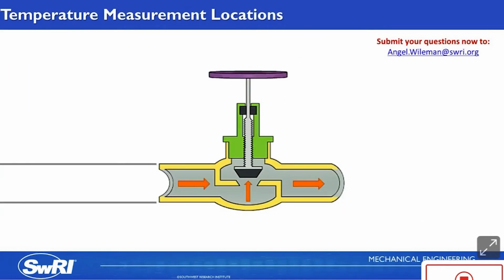The test standards have specific instructions on where to place the thermocouples for temperature measurement during testing. The first temperature reading is on the stuffing box by the stem seal. This is the primary temperature measurement point for API 624 testing, and it's used for information purposes as a reference measurement for the ISO standards. The second thermocouple is placed on the valve body exterior, and this is required by both ISO and API as a reference measurement.